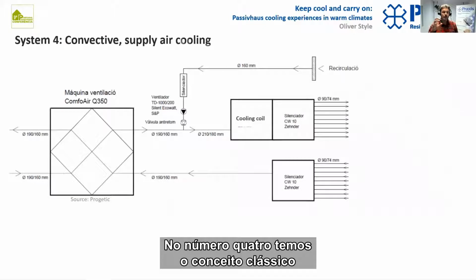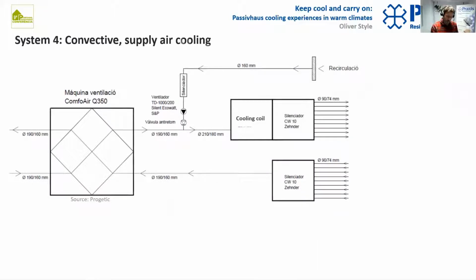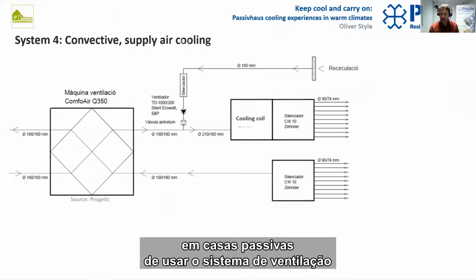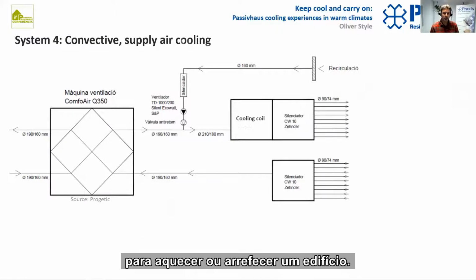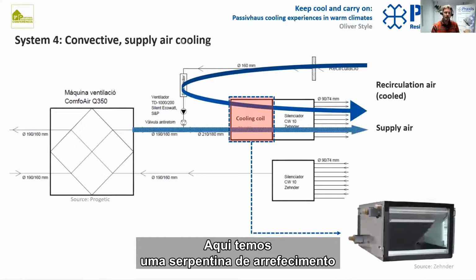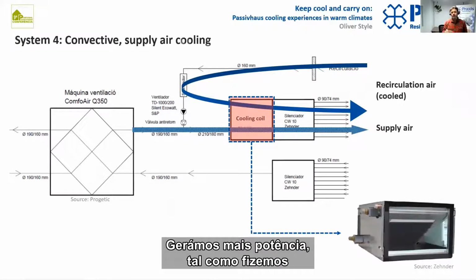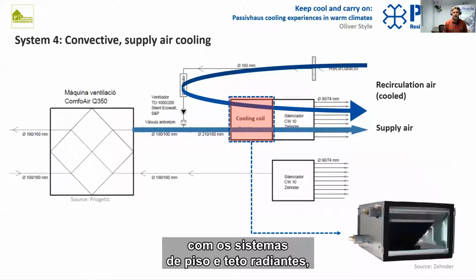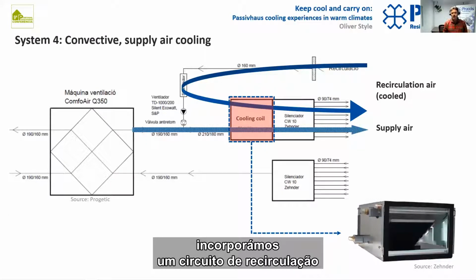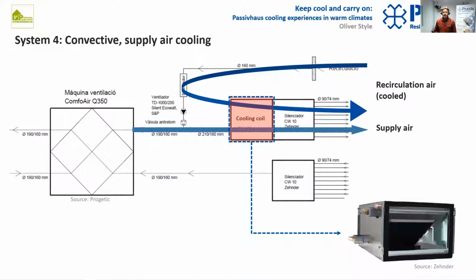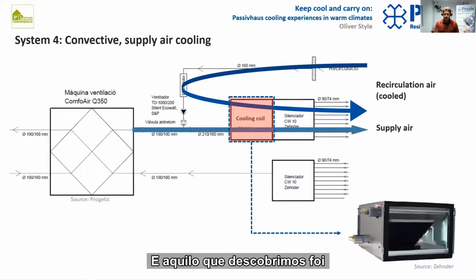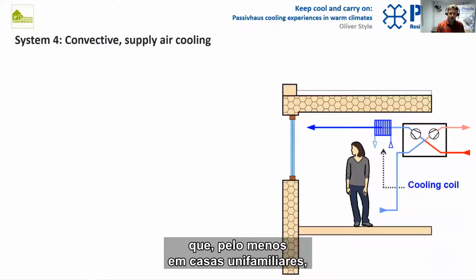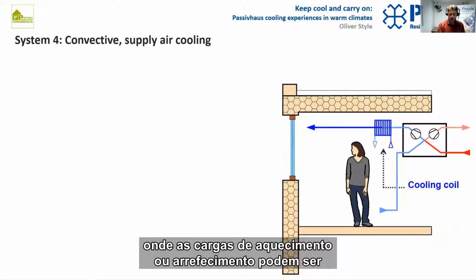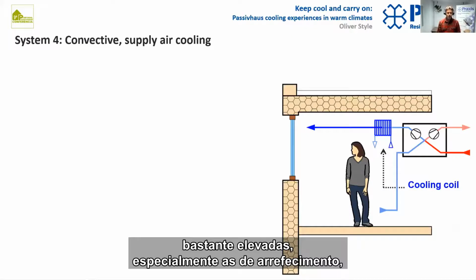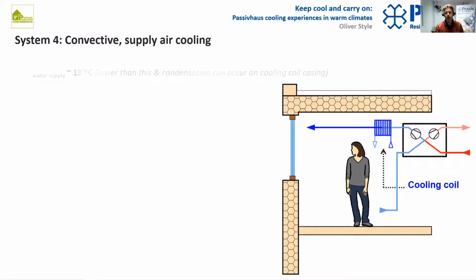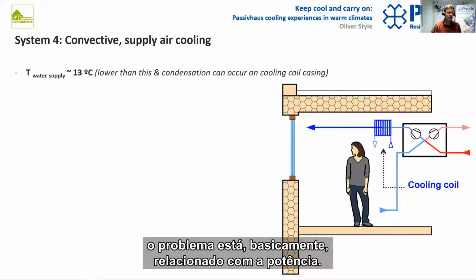System number 4, this is the classic passive house concept of using the ventilation system to heat or cool the building. So here a cooling coil is located in the supply air stream, and what we did also to provide more power, as we did with the radiant floor and ceiling systems, we incorporated a recirculation loop to increase power. Now what we found is that at least in single family homes where the heating cooling loads are fairly high, peak cooling loads can be quite high, the problem is basically to do with power.